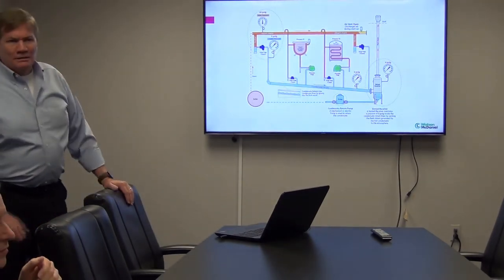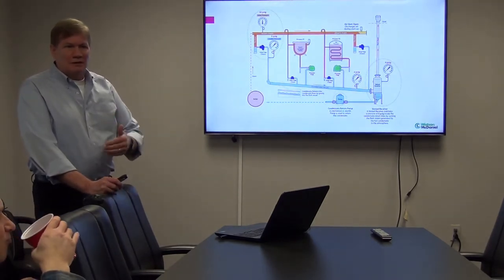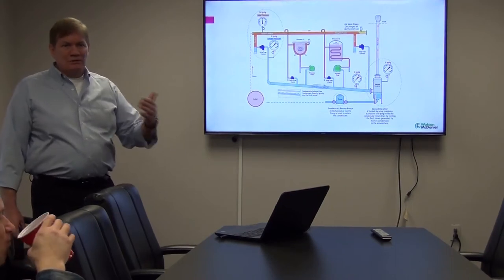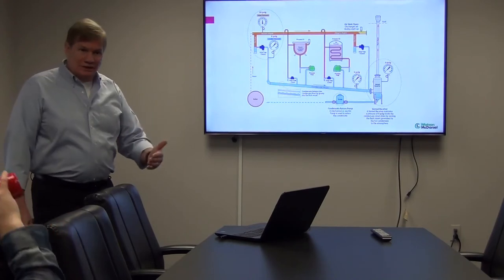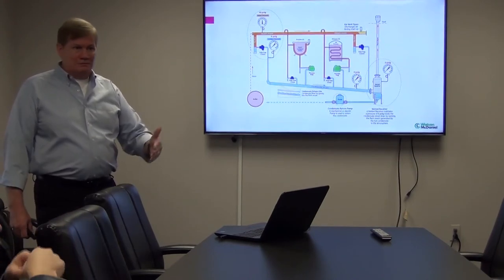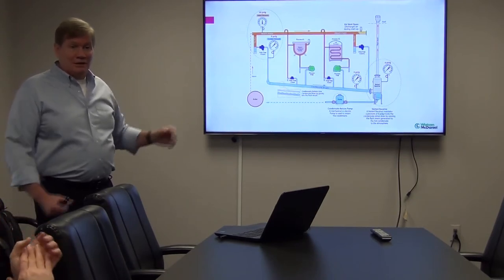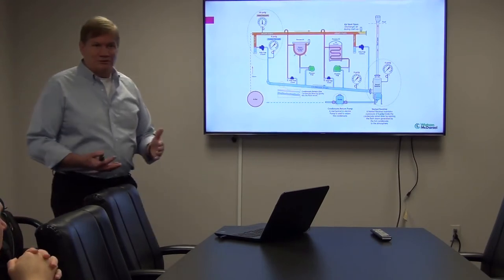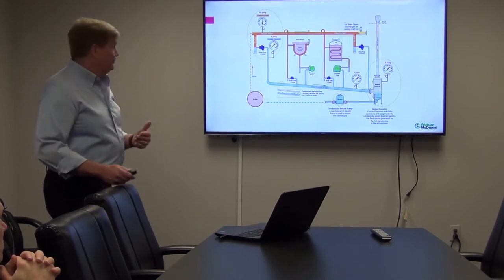How many? There's an analytical statistical calculation. On average, let's say if you had 100 traps in your facility, usually it's a 10% as a guideline, so every year you're going to have at least 10 failed traps in your system. So you let another year go by, 2 years, now you're at 20 failed traps. We'll see at the end here, it really costs you a lot of money. And the cost of the traps themselves versus the energy loss is really a savings right there. Now you're going to save a lot more money.